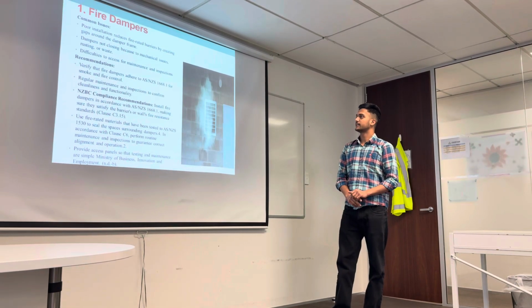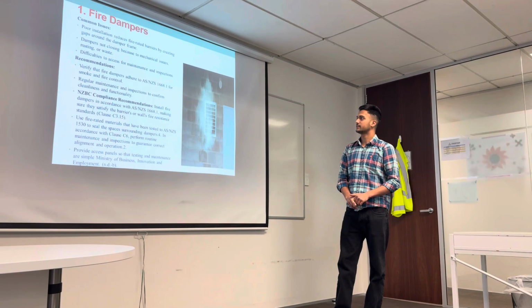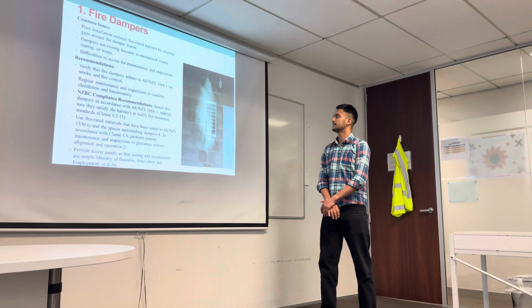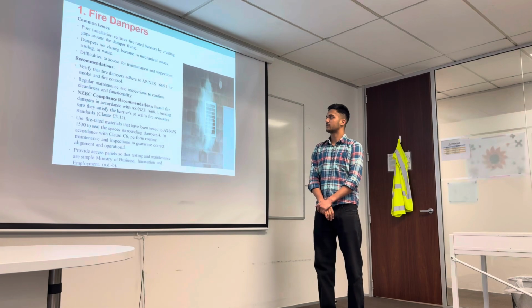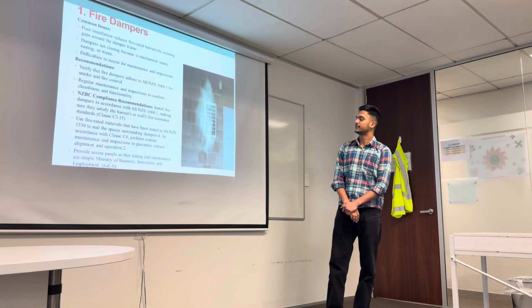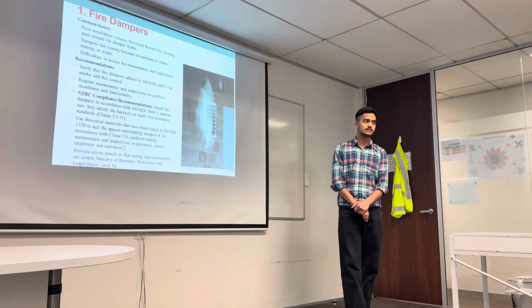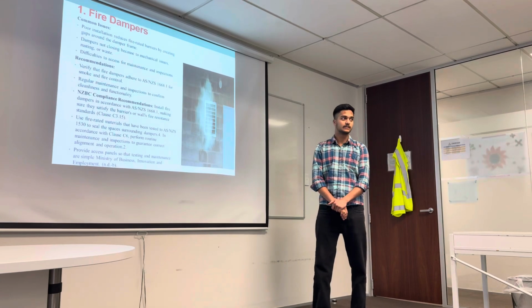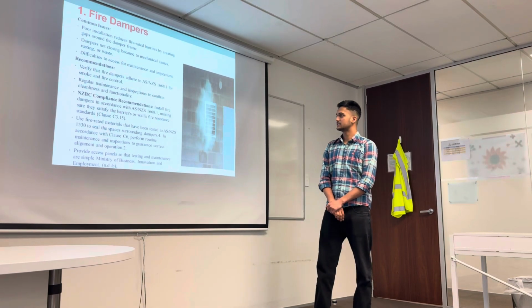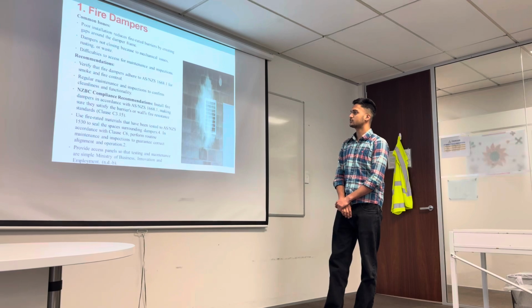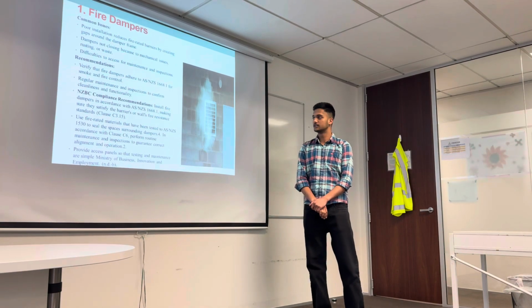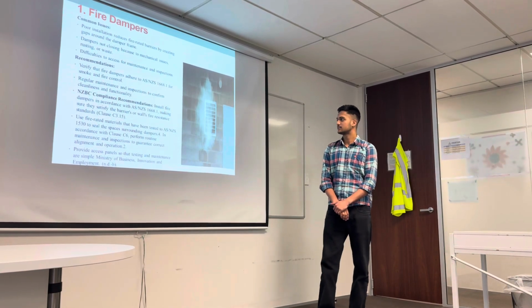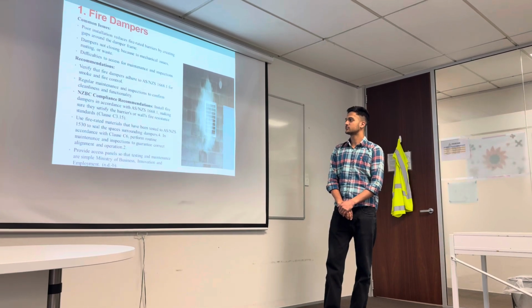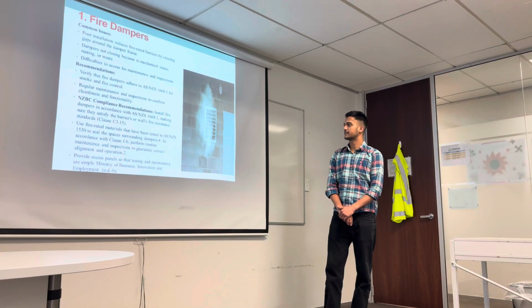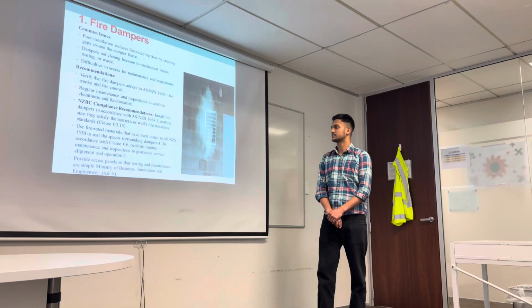Recommendations: verify that fire dampers adhere to AS/NZS 1668 for smoke and fire control, with regular maintenance and inspection to confirm fitness and functionality. NZBC compliance recommendation: install fire dampers in accordance with AS/NZS 1668, making sure they satisfy the fire resistance standards of the barriers or walls.